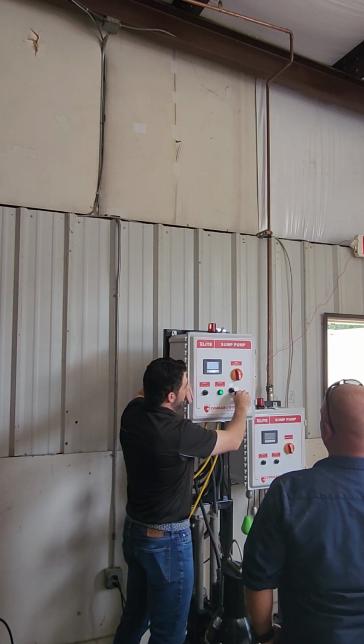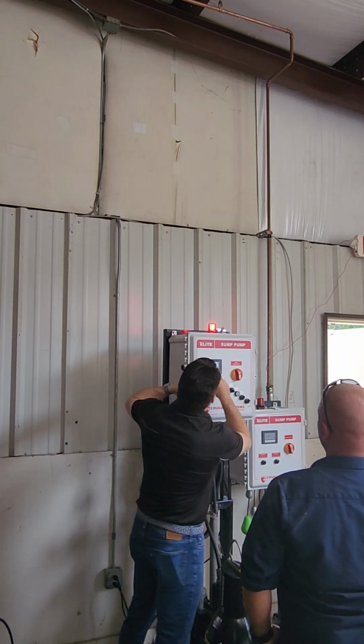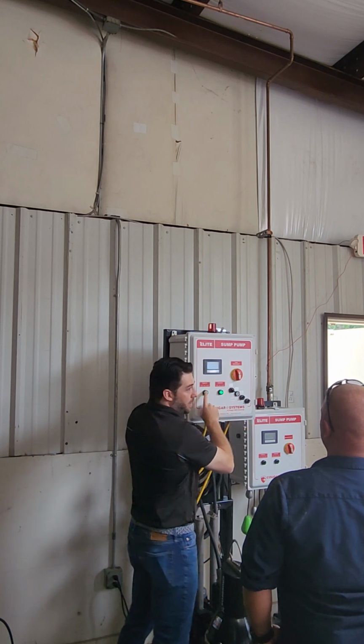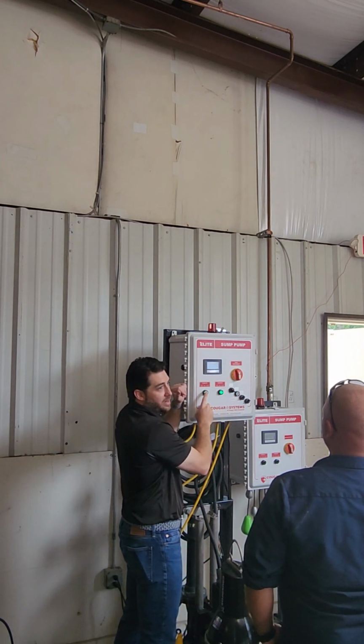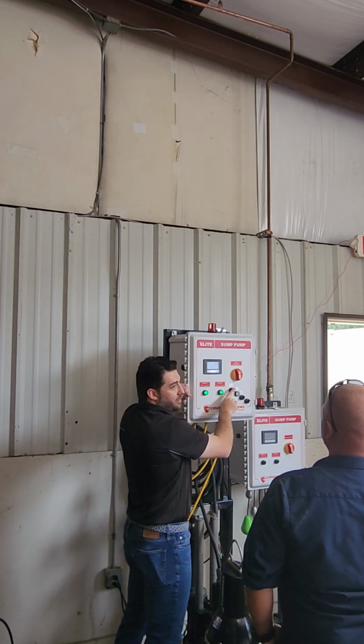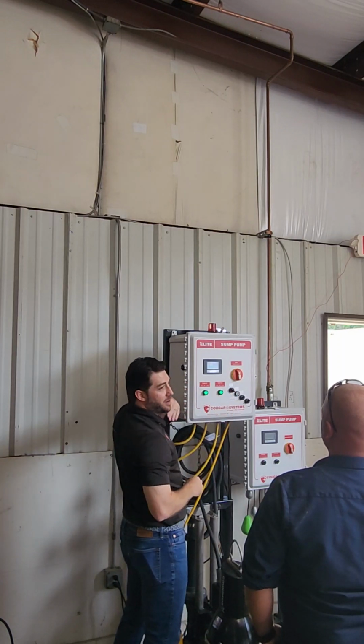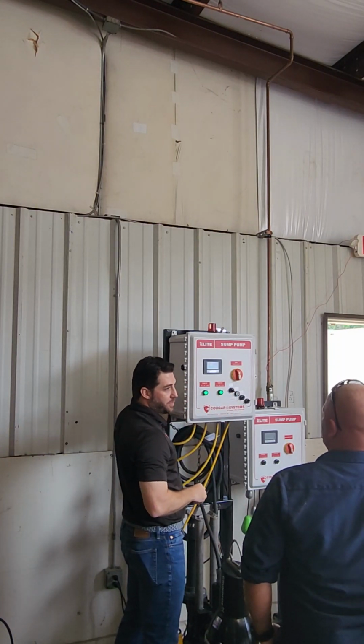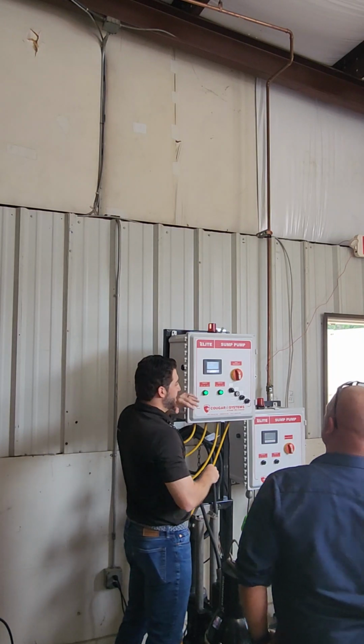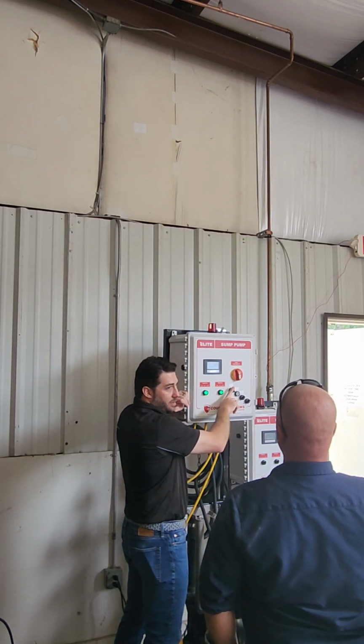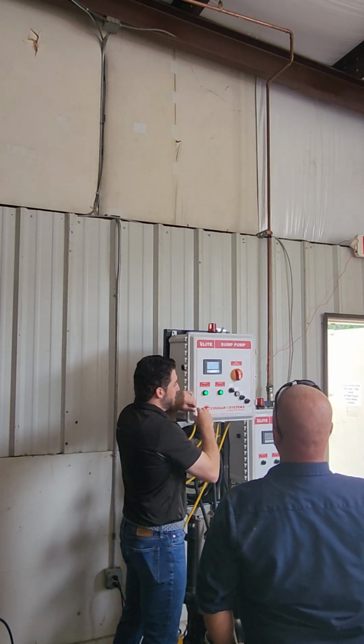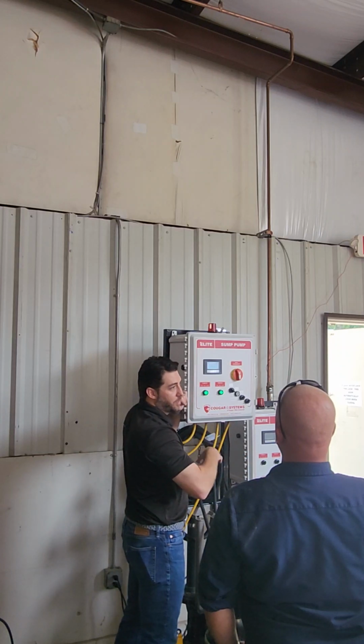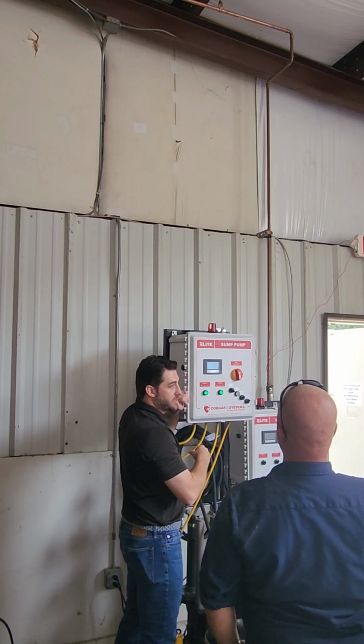Okay, so now we're going to hit the lag pump again, and you can see we got that lag pump alarm because we hit the lag pump twice. So even though we never got to the high level alarm, it let us know, hey, you have an issue because your lag pump has come on too many times. Okay, so that's how we're able to leave the alarm, the top one, but still give an alarm if one of the pumps isn't working. Does that make sense? Yeah.